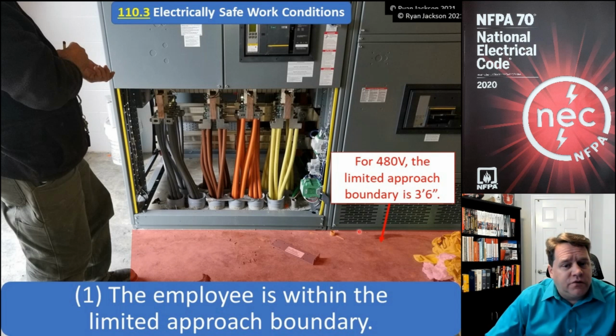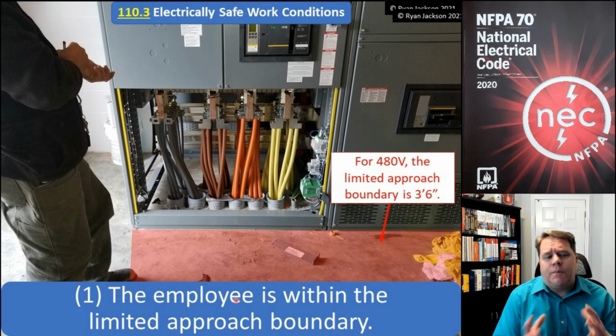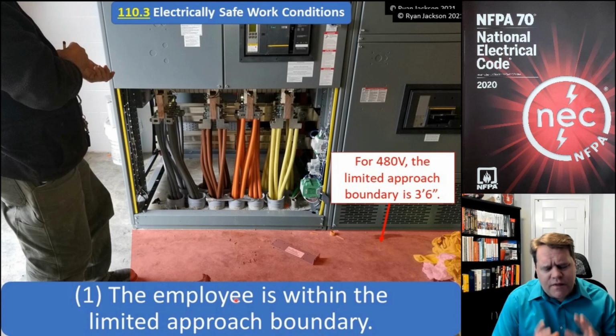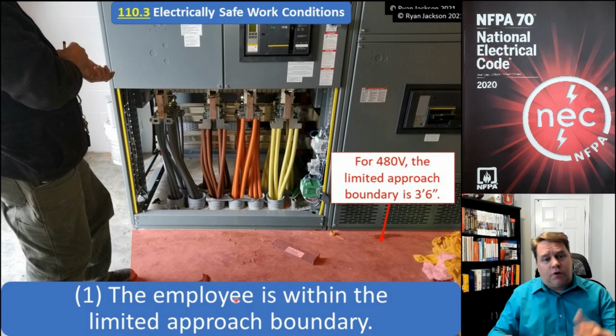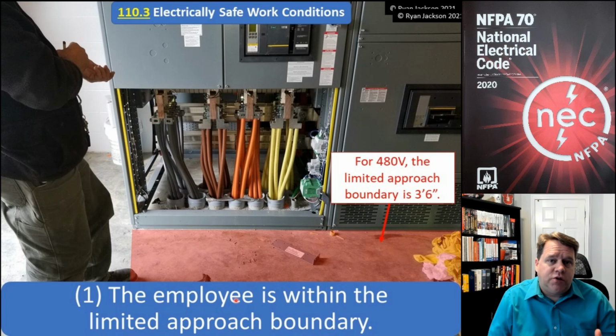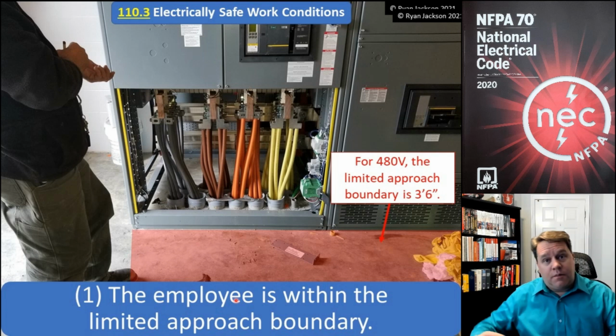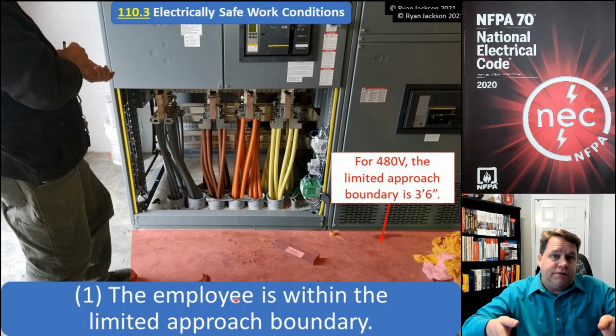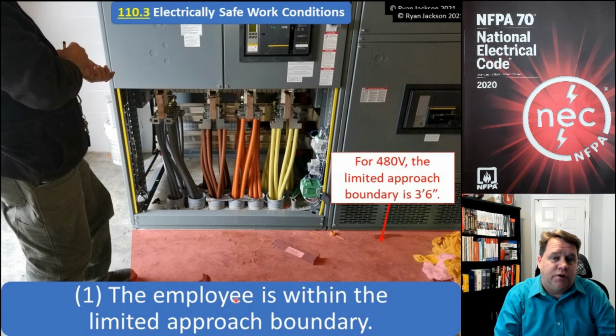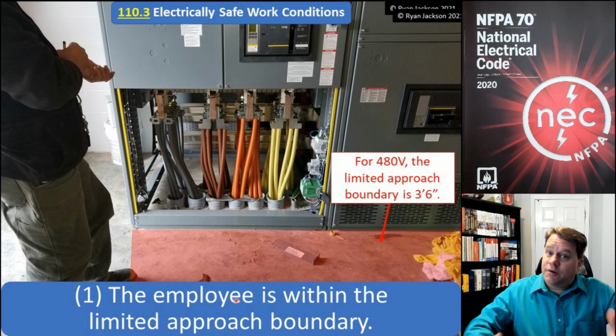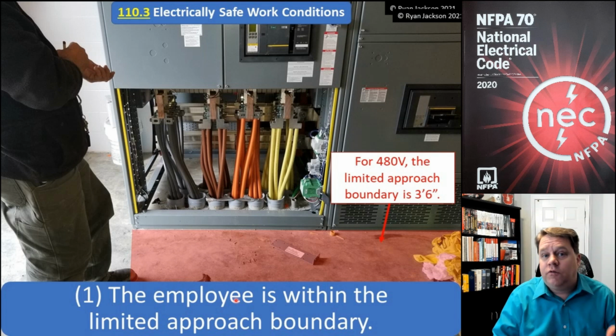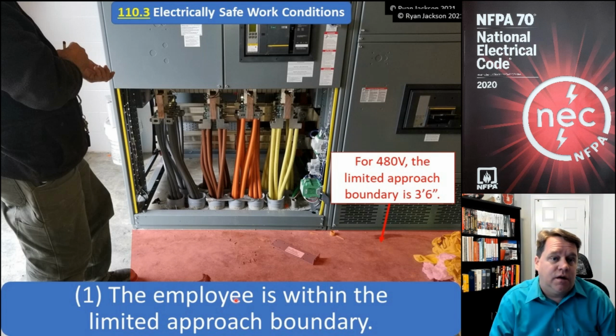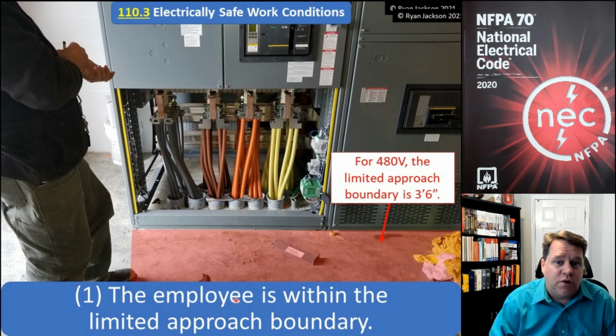Now, for 480 volts, that boundary is 3'6". And if you stop and think about it for a minute, that's a pretty reasonable requirement. If you've removed the cover off of the switchboard here and you're within 3'6", so pretty much the working space, I mean, if you're within 3'6" of the energized 480 volt equipment, you're pretty much right in there. You really need to have that thing shut off and put into an electrically safe work condition.